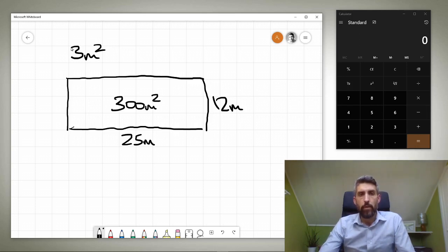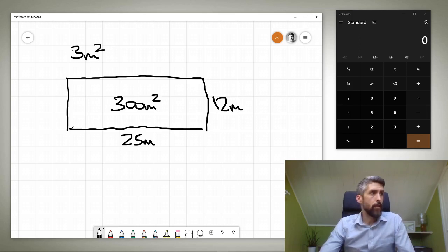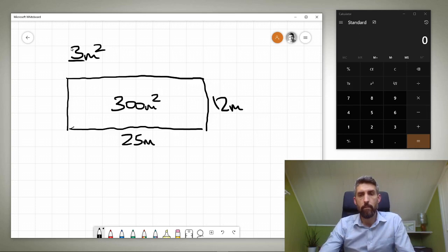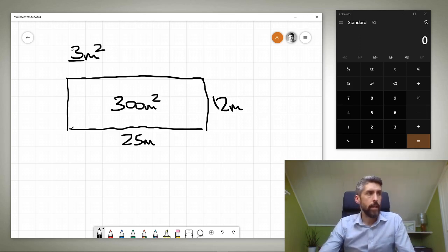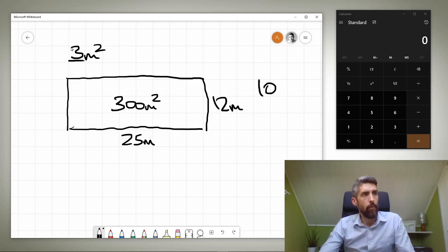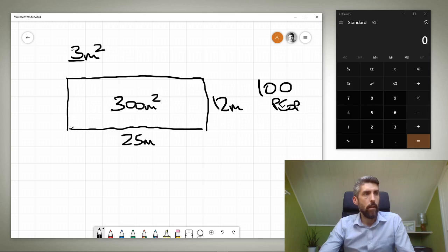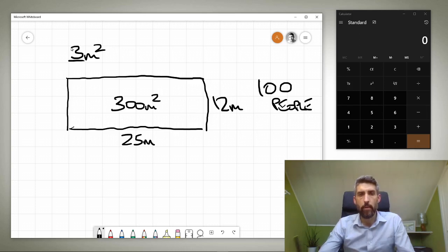So 300 square meters divided by 3 to allow for that 3 square meters of space per person is going to give us a maximum bather load of 100 people. This is only a guide though. This is a starting point.